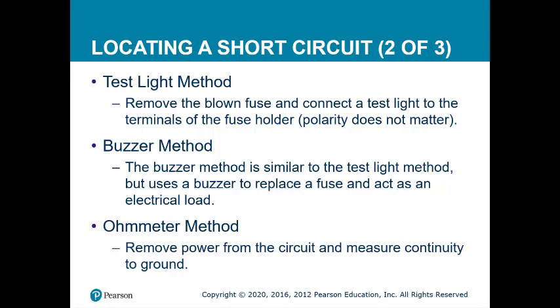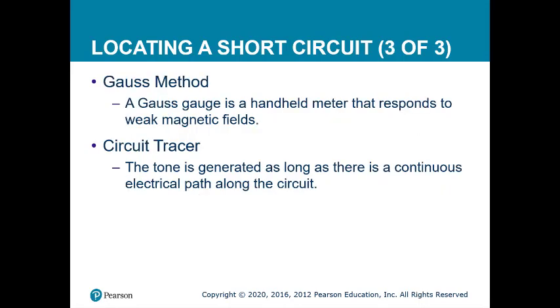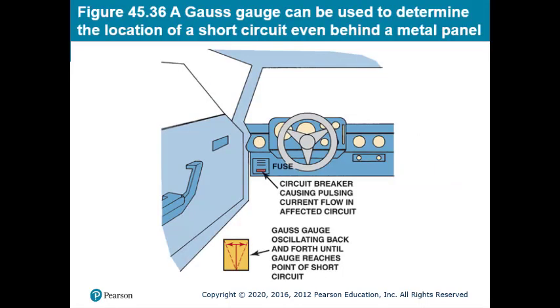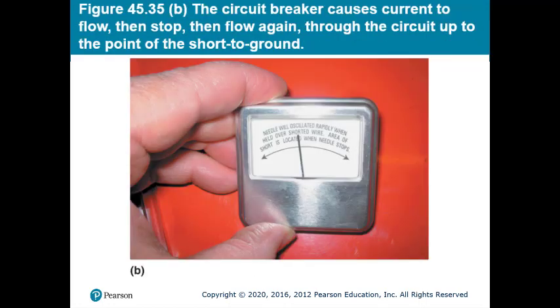And then there's the ohm meter method, which is very similar to the test light and the buzzer method, but instead of a light and instead of a buzzer sound, you'll see continuity on the meter. When you finally find the short and remove it, then the meter should say OL. There's also a Gauss method where you're going to use a circuit breaker at the same time, and just before the circuit breaker trips, you'll actually pick up the magnetic field on the Gauss gauge, and eventually when you stop picking up the magnetic field, you found the location of the short.